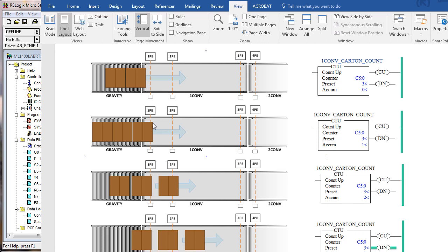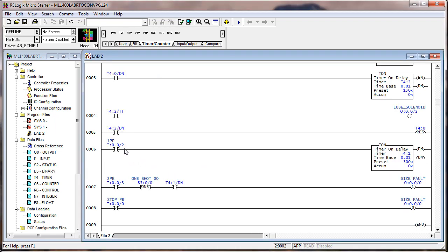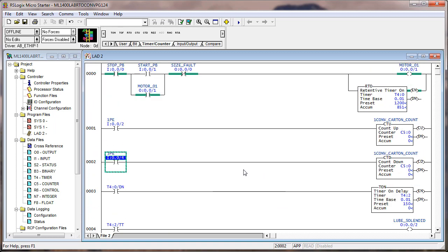But for right now, we're doing it with the most obvious logic. Typically, this is what you would do. And then later on, you would say, okay, wait a minute, the system shut down and that carton wasn't really on there. And then it started back up and somehow got counted twice or something. So typically, we would use the trailing edge of the carton to say that it has arrived, not the leading edge. But for right now, this is good. So you see, we're incrementing our accumulate value. And we're doing this with the switches that operate the photo eyes. Because remember, we don't actually have cartons and photo eyes. We do have the motor running. And we have one PE and three PE that do the count up. So I could also operate one PE and two PE to do the size fault. I'm not going to convolute this whole process. I'm just going to use one and three PE.